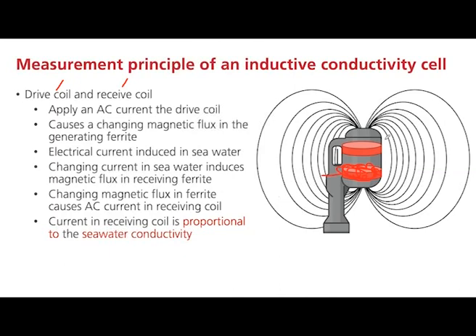That current, as it passes through the other coil, induces a signal inside this coil, inside this ferrite, which is picked up by this coil and then measured. The upshot of this is that we induce a current with one and we measure it with the other. The strength of the response measured by the pickup coil is proportional to the conductivity of the seawater. Actually, the conductance, but we then apply a cell constant to get a conductivity from it. That's really the basic thing here, and it's fundamentally a linear system too, which is very important for calibration reasons.